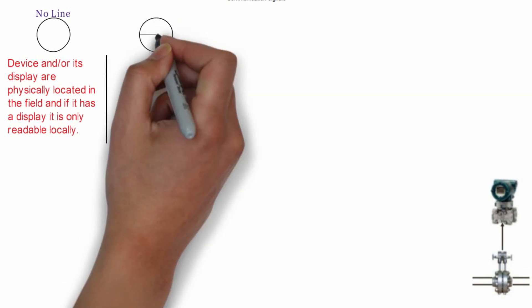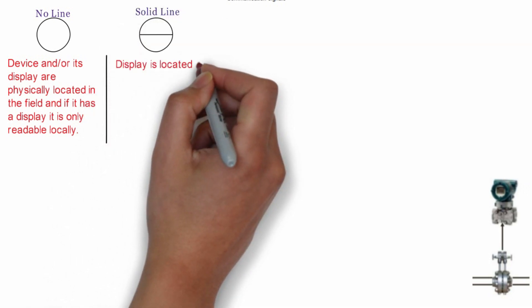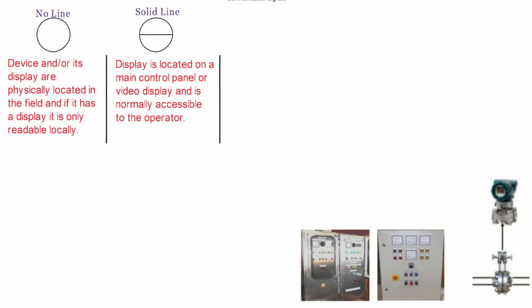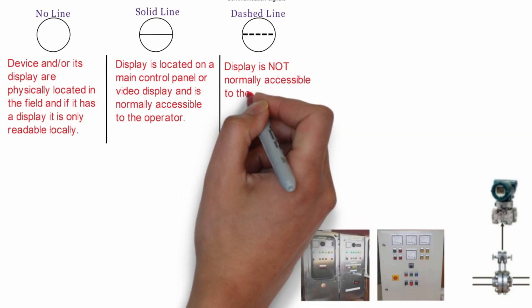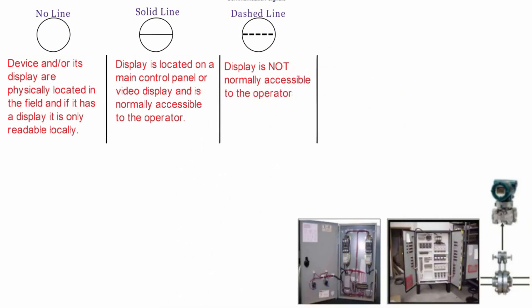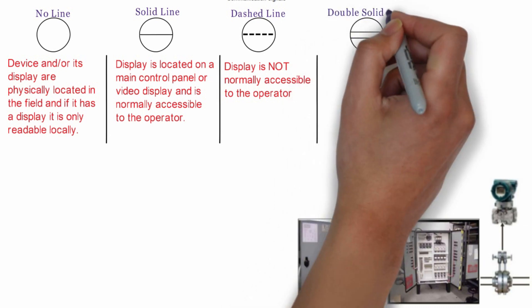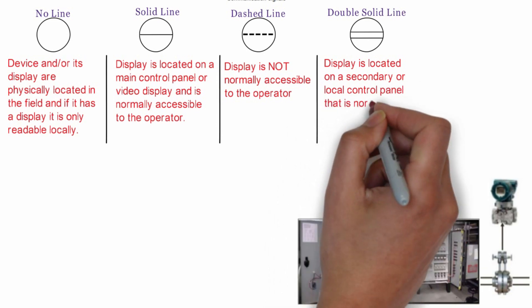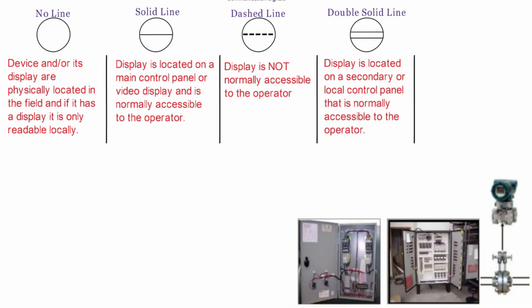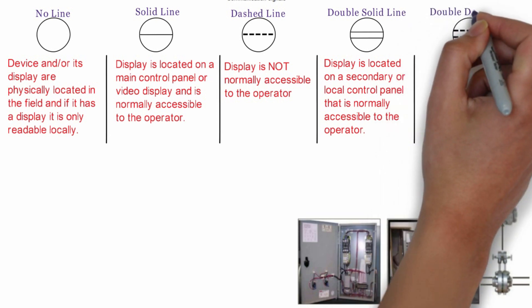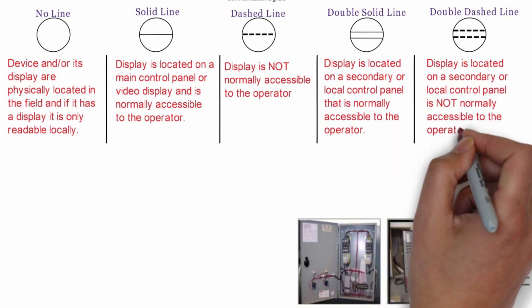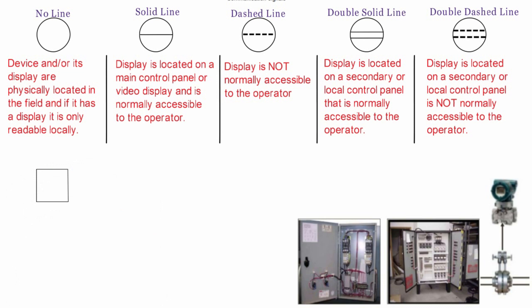A solid line in the bubble means that the display is located on a main control panel or video display and is normally accessible to the operator. A dashed line in a circle means that the display is not normally accessible to the operator. A double solid line in the circle means that the display is located on a secondary or local control panel that is normally accessible to the operator. A double dashed line means that the display is located in a secondary control panel and is not normally accessible to the operator.